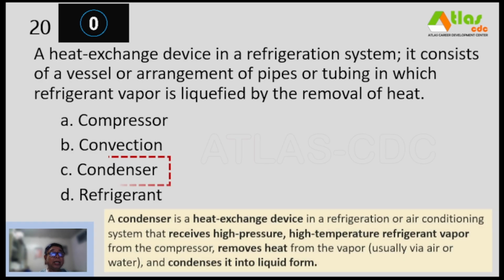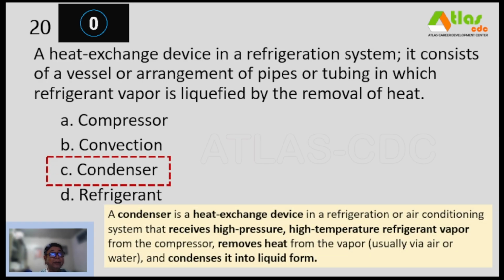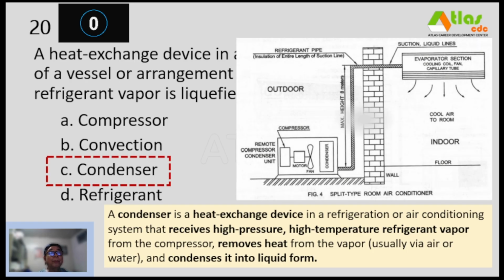And our correct answer is letter C, condenser. So it is a heat exchange device in a refrigeration or air conditioning system that receives high pressure, high temperature refrigerant vapor from the compressor and removes heat from the vapor, usually via air or water, and condenses it into liquid form. Ito yan. Ang condenser ay yung nasa labas. So, yung fan, binoblow niya yung mga pipes para matanggal yung init doon sa piping at lumamig yung refrigerant bago ibalik doon sa papunta sa may evaporator.